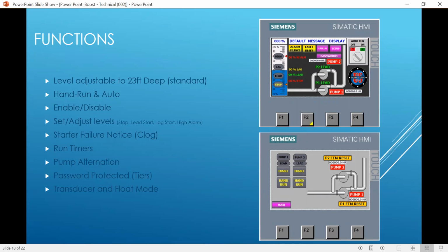But if you're a person who's designing a large project and you've got 3 or 4 buildings, and you do have the SCADA control, and you also have some kind of a BACnet or a Modbus connection to the main building control, this thing is ideal because it already speaks BACnet and it's already set up to go. So if you have an HOA panel, obviously that's not going to happen.